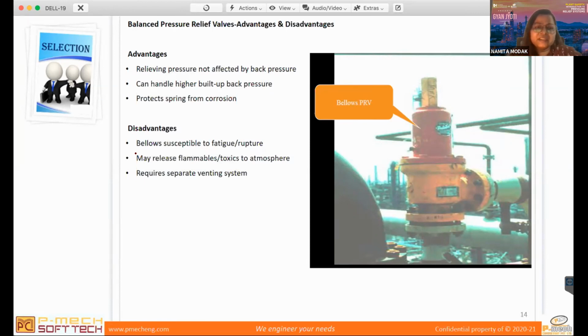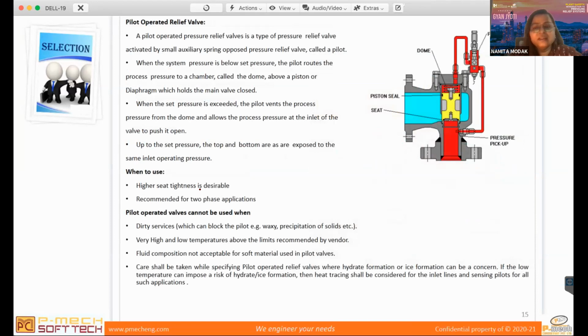The disadvantage: the bellows is susceptible to fatigue and rupture. So that is a disadvantage of it. It may release flammable or toxic fluid to the atmosphere and requires a separate venting system. You will see there is an additional vent given to the balanced bellows. Now the pilot operated, this is the costliest among all three.